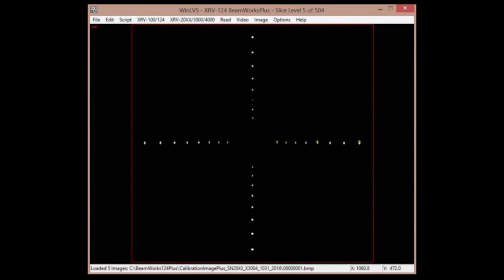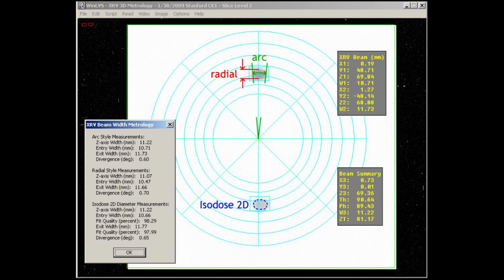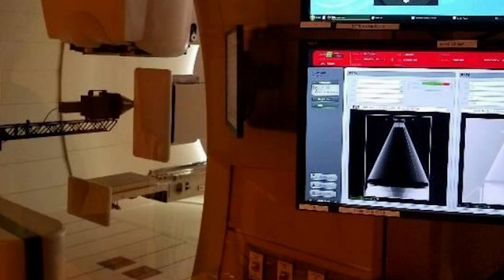This image forms a precise pattern that enables the BeamWorks software to map 2D pixels from the camera onto the virtual 3D model of the imaging cone. The calibration process is described in Section 4.8 of the BeamWorks manual and should be performed at least once per year or after the XRV-124 has been subjected to strong vibration, like being moved between facilities. A complete XRV-124 end-to-end test will need to use the KV imaging subsystem during the proton or LINAC diagnostic delivery.